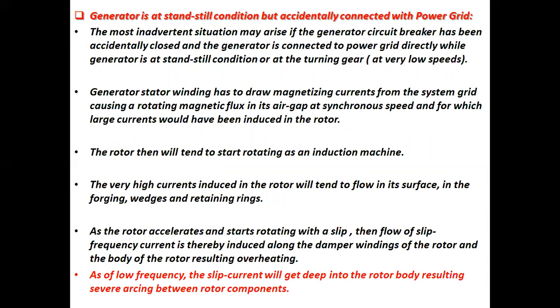If the generator is at standstill condition but accidentally connected to the power grid, the most inadvertent situation may arise if the generator circuit breaker has been accidentally closed and the generator is connected to the power grid directly, while the generator is at standstill condition or at turning gear, that is at very low speeds. The generator stator winding has to draw magnetizing currents from the system grid, causing a rotating magnetic flux in its air gap at synchronous speed, for which large currents would be induced in the rotor.